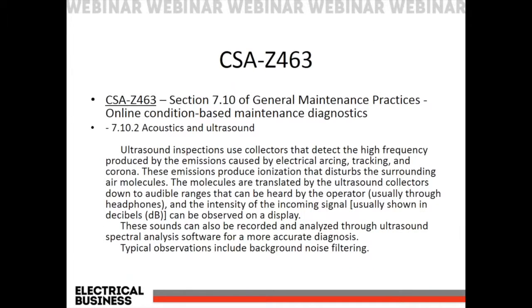One thing I like to show people, with a lot of electrical gurus that I deal with in Canada, is that this became a big deal back in December of 2013 when CSA Z463 was introduced, which talks about electrical maintenance safety practices for Canada. You can see that in CSA Z463, ultrasound is actually mentioned, and this is becoming an official standard. An important thing about this is that we are a recognized technology to be used in online testing. Even though CSA Z462 says it's better to test offline, when we have to test online, we can use our technology along with infrared to diagnose problems with those electrical assets.